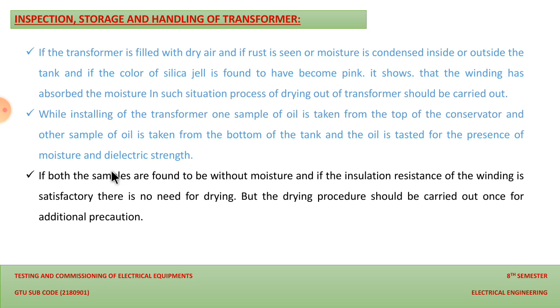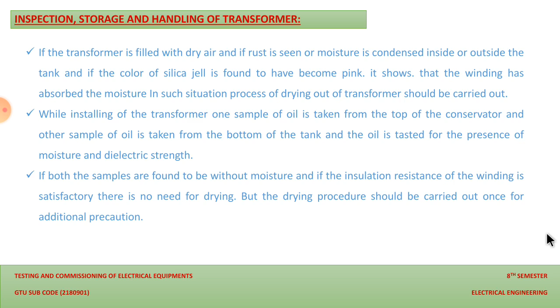So yes, after certain tests on the transformer oil, say the transformer oil breakdown test, if you find the dielectric strength of the oil is proper, then there is no need to carry out the drying out procedure. But the drying procedure can be carried out once as an additional precaution. So if you want to take an additional precaution, you can carry out the drying out process before you take your transformer into use at your site. So these are the points that you should check for the inspection.